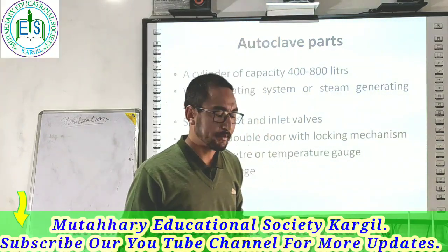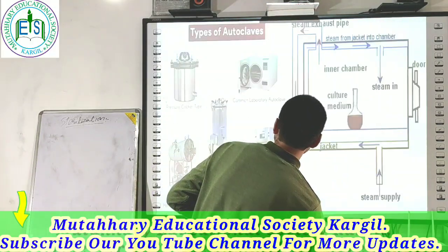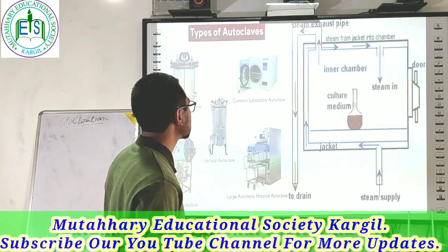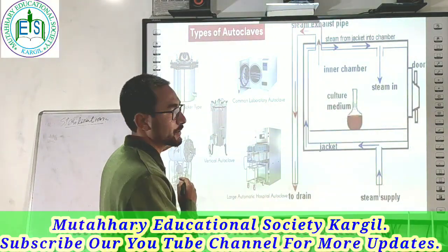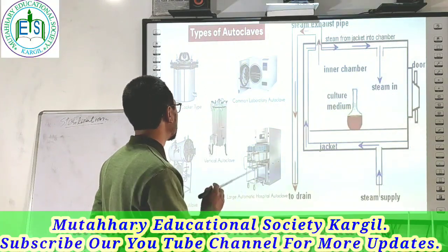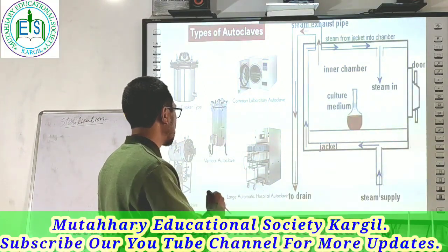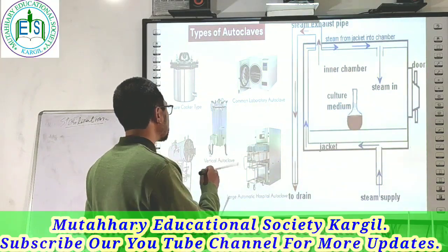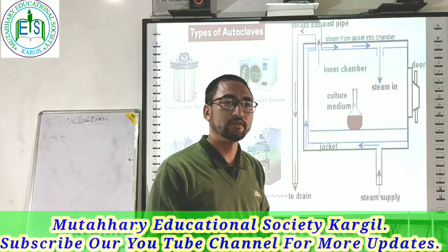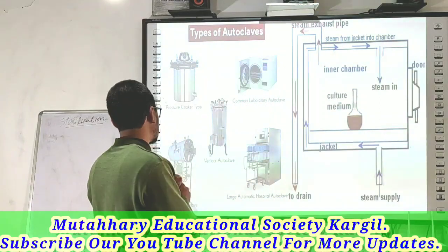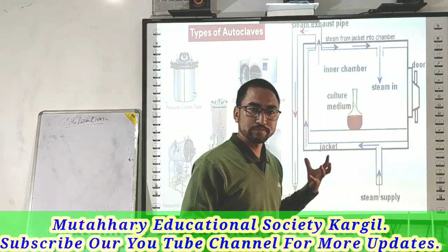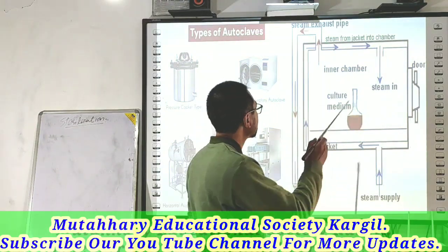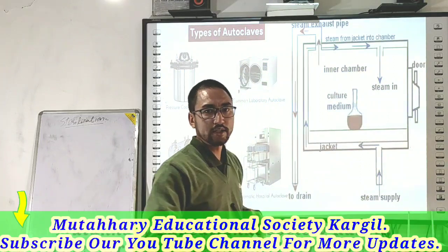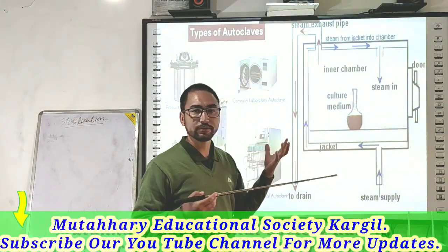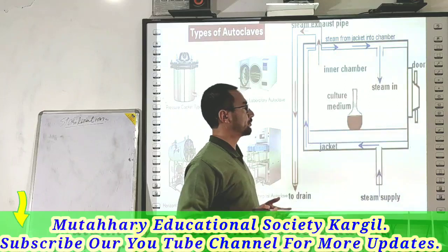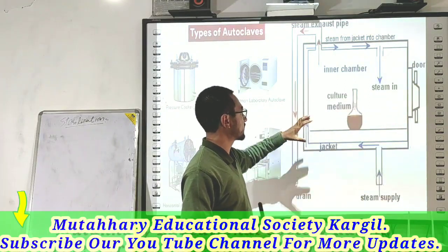An autoclave itself has different parts. This is how the diagrams of various types of autoclave look. There's a pressure cooker type autoclave, a common laboratory autoclave, which is vertical, and a large automated hospital autoclave. These are mostly used in hospitals to autoclave various surgical items, and these are horizontal-type autoclaves. Now, how the structure functions is something like this. You have an inner chamber. Within the inner chamber, for example, if you have to sterilize your culture media, you will put the culture media within this.